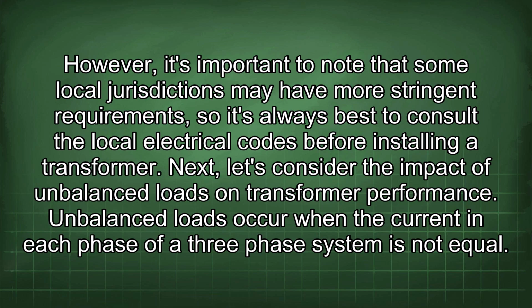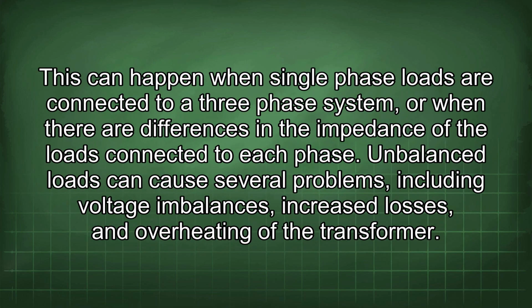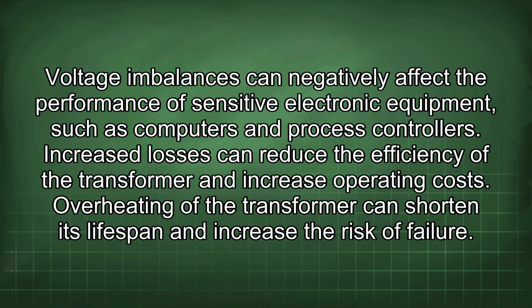Next, let's consider the impact of unbalanced loads on transformer performance. Unbalanced loads occur when the current in each phase of a three-phase system is not equal. This can happen when single-phase loads are connected to a three-phase system, or when there are differences in the impedance of the loads connected to each phase. Unbalanced loads can cause several problems, including voltage imbalances, increased losses, and overheating of the transformer. Voltage imbalances can negatively affect the performance of sensitive electronic equipment, such as computers and process controllers. Increased losses can reduce the efficiency of the transformer and increase operating costs. Overheating of the transformer can shorten its lifespan and increase the risk of failure.